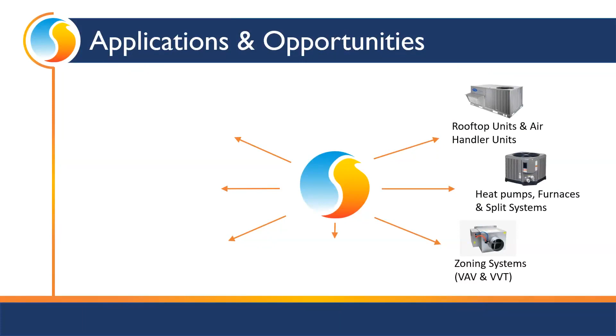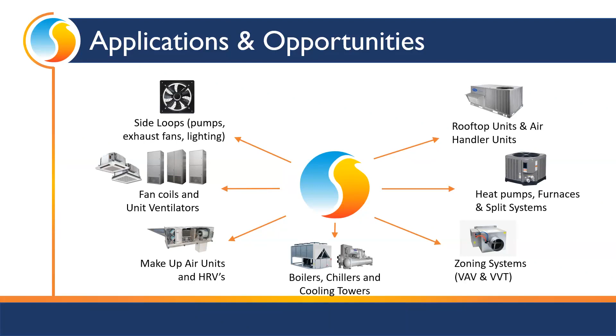Fan coil units, unit ventilators, and then one of the big things - it seems like every single one of these projects we do, there's some sort of little valve or damper or fan that just doesn't fit into this predefined box we have set up for all these other controllers. Remember we talked about application specific and pre-programming - well, we have a side loop controller where we can build our own logic to pick up these little side loops. Everything is tied together with the free software and applications.